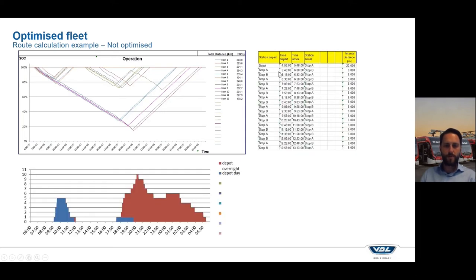This is an example of how the time schedule can look like that we get from the customer with all the trips from point A to point B. And this is an overview of the charge operation. So this bus operation will result in this charge operation on the depot. This peak is the overnight charging during the morning, and this is at the end of the evening and the night charge of all the buses. So it shows that in the morning you need five chargers and in the evening you would need 10 chargers to charge the 12 buses.